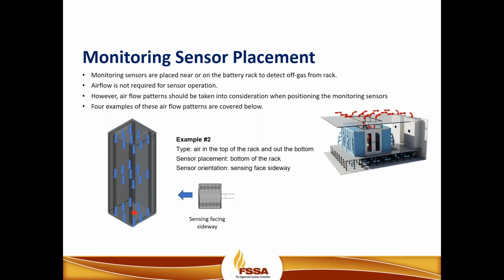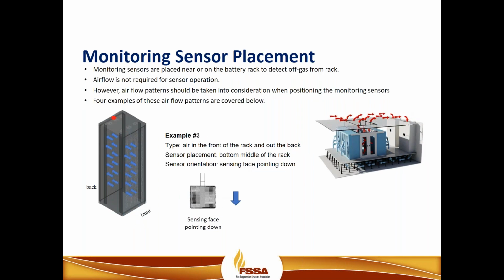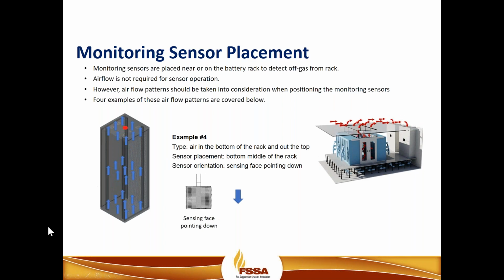If you're cooling from the top to the bottom, you place the sensor in the bottom of the unit facing up, I'm sorry, facing sideways to eliminate or reduce the potential for contamination to the sensor. If you're cooling from the front to the back, you want to place the sensor in the back of the unit at the top of the unit. And then of course, if you're cooling from the bottom to the top, you want to place the sensor at the top of the unit facing down in the path of airflow.